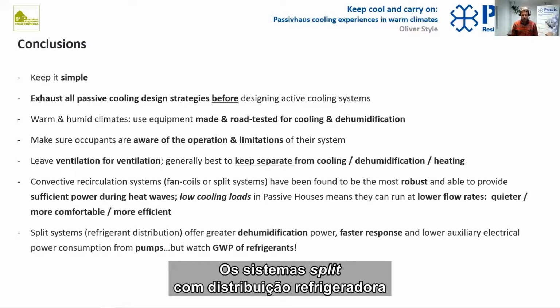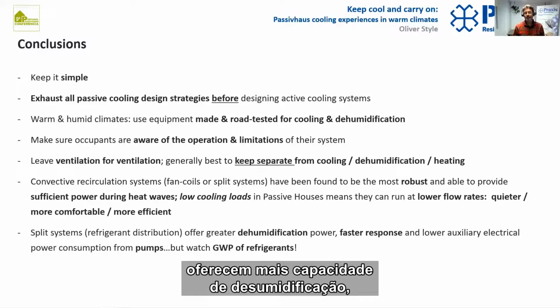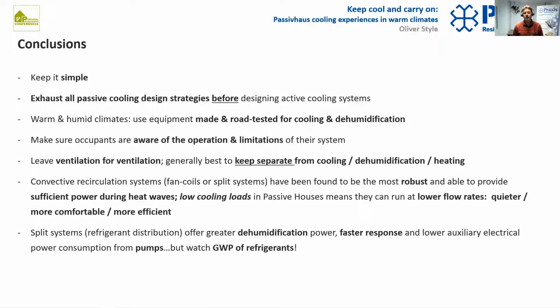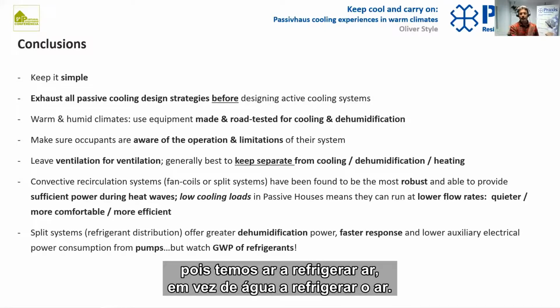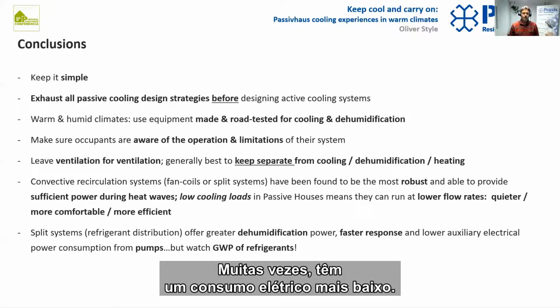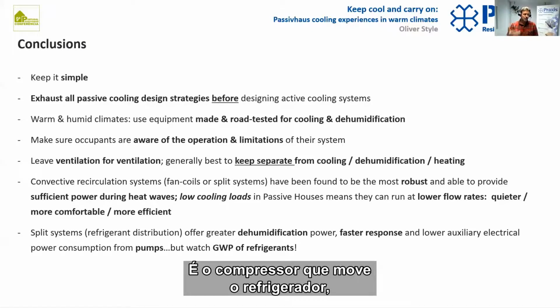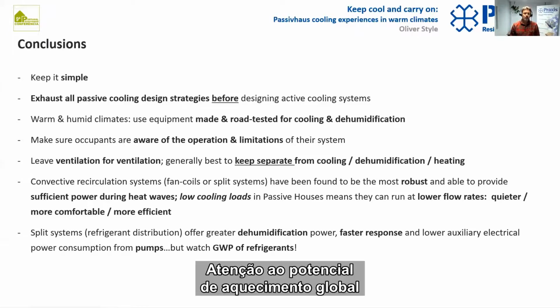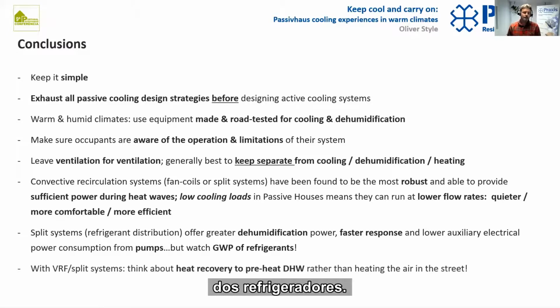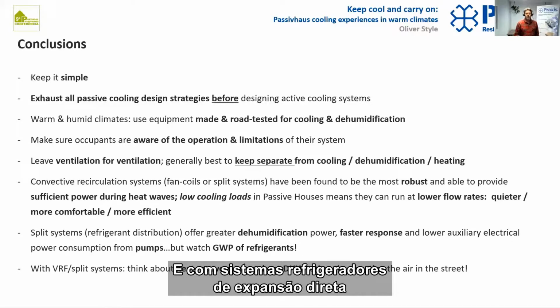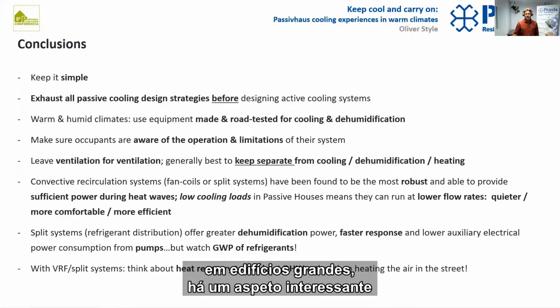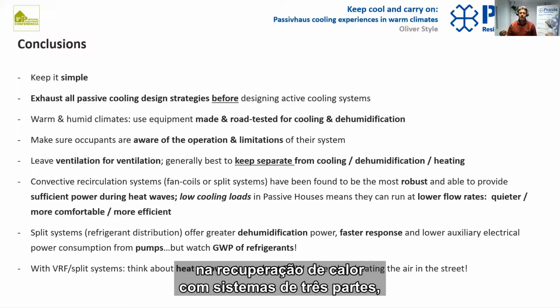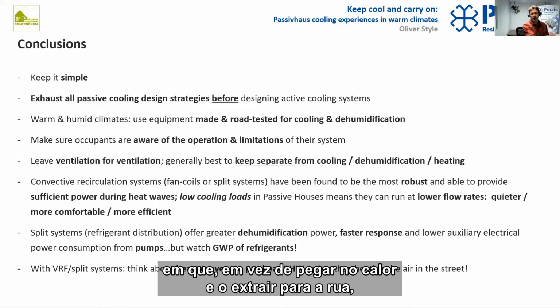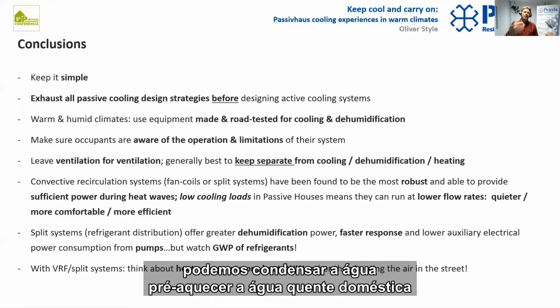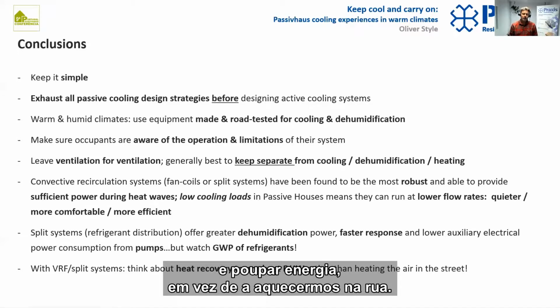Split systems with a refrigerant distribution offer greater dehumidification power, which can be useful in humid climates. They offer a faster response. You're going air, refrigerant, air instead of air, water, refrigerant, air. And they will also have lower auxiliary electrical power consumption from pumps. The compressor is moving the refrigerant around, not a pump moving water, and so on. But important again to watch the global warming potential of refrigerants. And with direct expansion or variable refrigerant flow systems in larger buildings, it's interesting to think about heat recovery with 3-pipe systems in which instead of taking heat and dumping it to the outside air in the street, we can condense to water and preheat domestic hot water and save energy rather than heating air in the street.